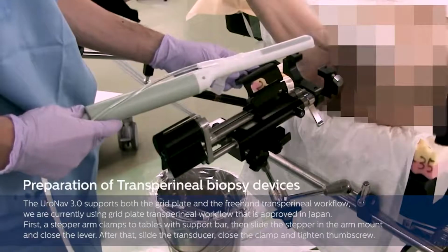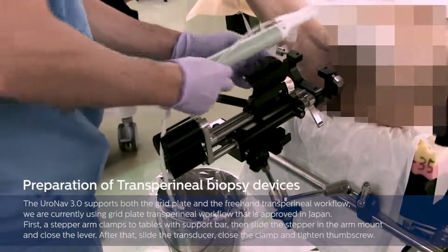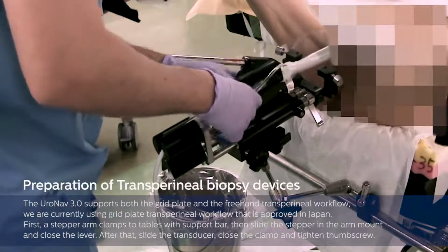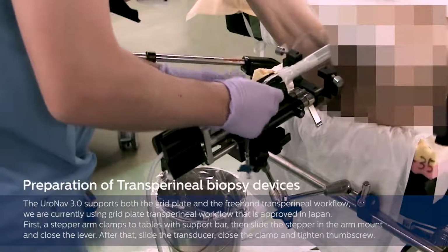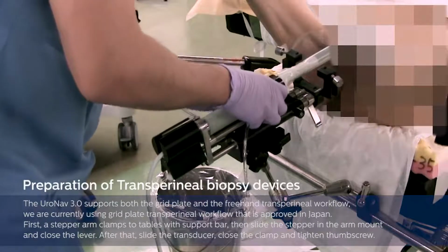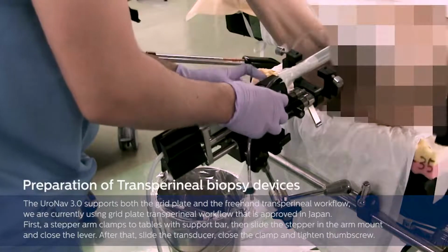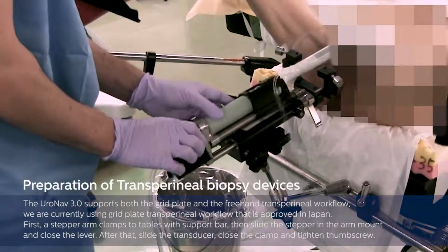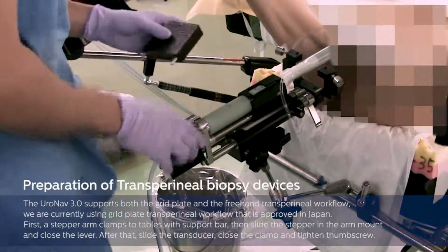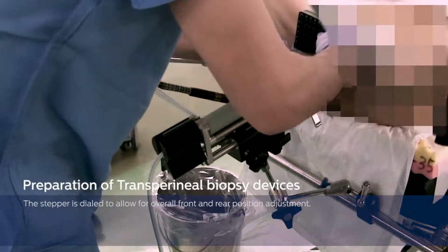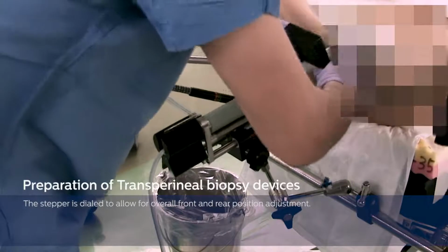The UroNav 3.0 supports both the grid plate and the freehand transperineal workflow. We are currently using grid plate transperineal workflow that is approved in Japan. First, a stepper arm clamps to tables with support bar, then slide the stepper in the arm mount and close the lever. After that, slide the transducer, close the clamp and tighten thumb screw. The stepper is dialed to allow for overall front and rear position adjustment.